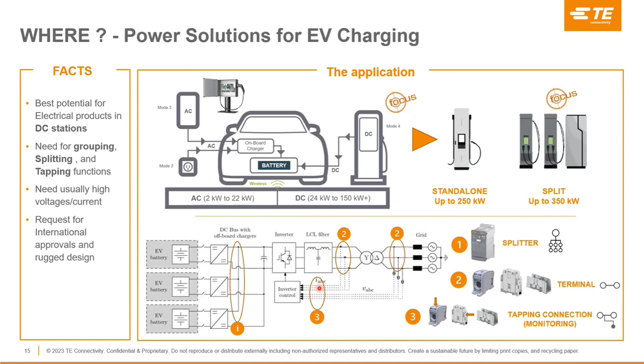The third function shown here is particularly interesting, something you can propose along with these power blocks. Most of them are equipped with an extra connection we call a tap connection, which takes a little part of the power from the main source and drives it to a controller or monitoring device, since most of these devices need feedback from the network to check its quality. You need the ability on these power blocks to tap the power and survey the voltage on the line. Altogether, these are the three functions you can use.